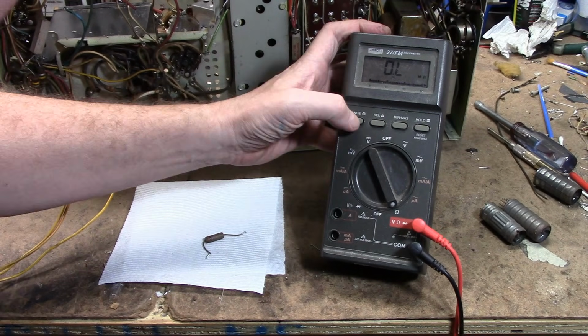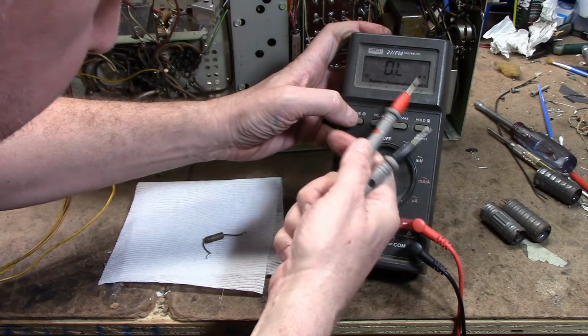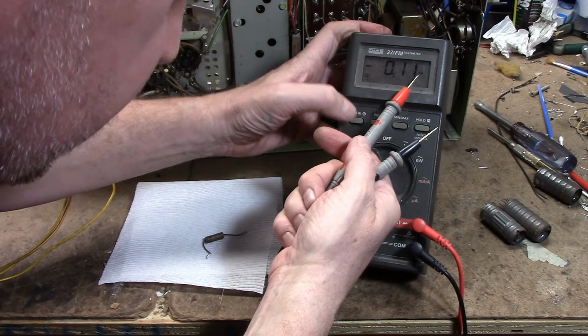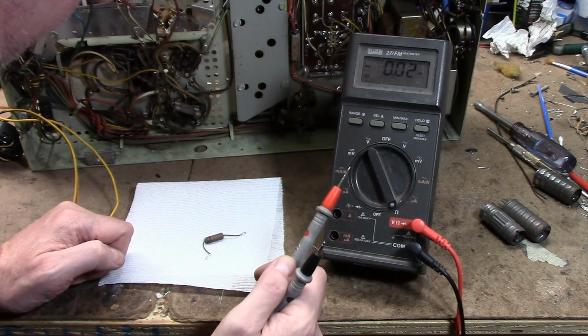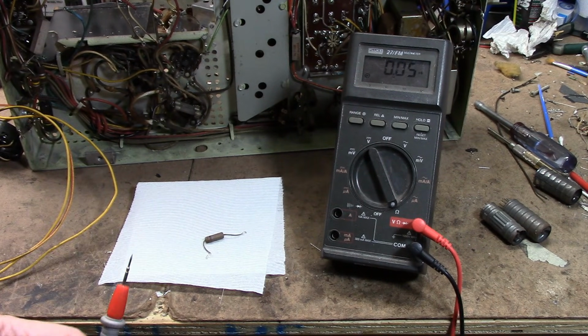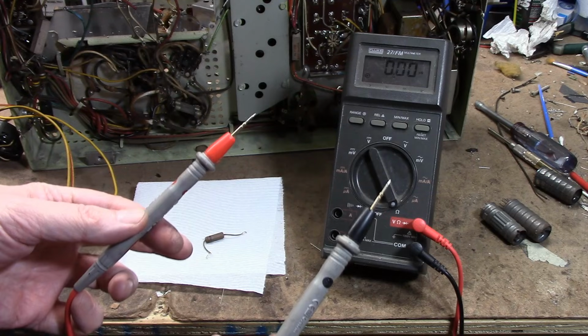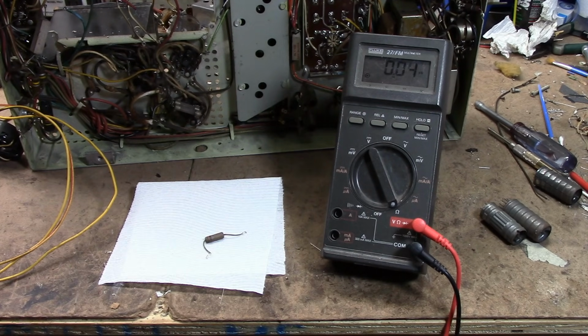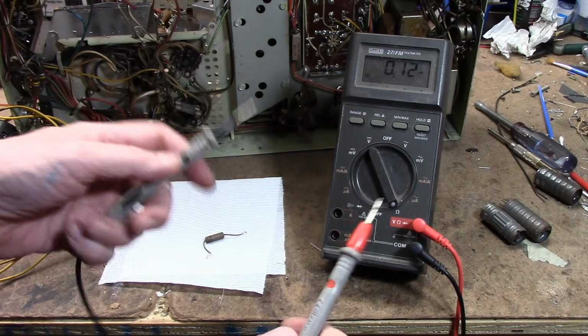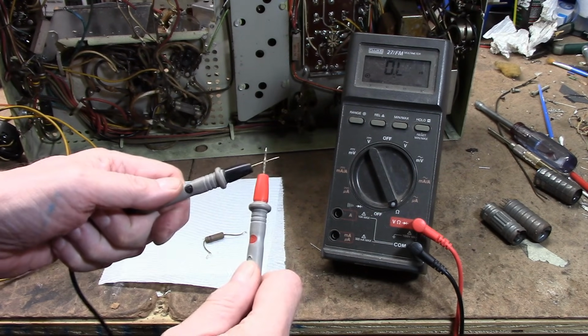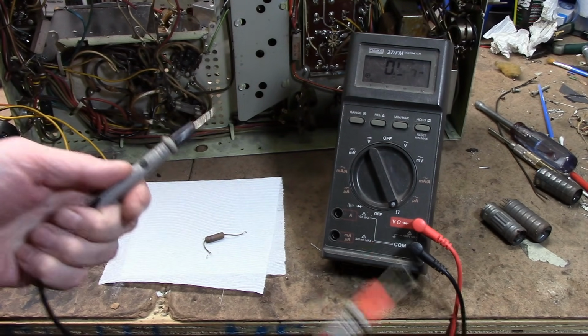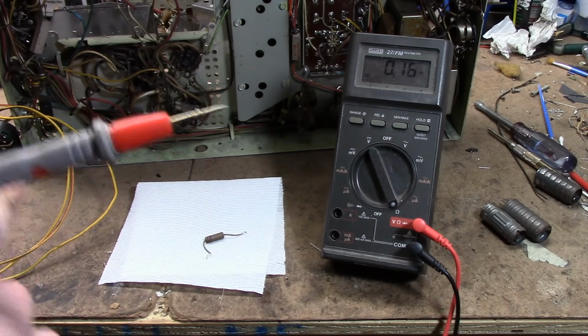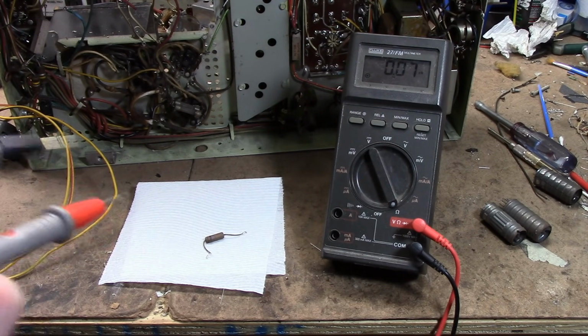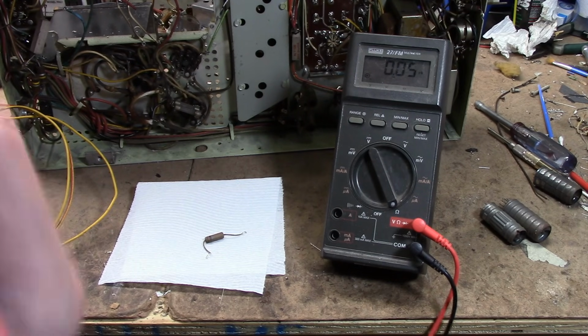But there's a little known feature on these: if you hit range a few times, watch, it switches from mega ohm to nS, small n capital S. It's jumping around, but basically reads 0 with the probes not connected. That's conductance, nanosiemens, the inverse of resistance. If it's open it reads 0, and if you short it, it goes to infinity. It's the opposite of resistance. In this mode it can measure up to 100,000 mega ohms. You just have to do a little math.